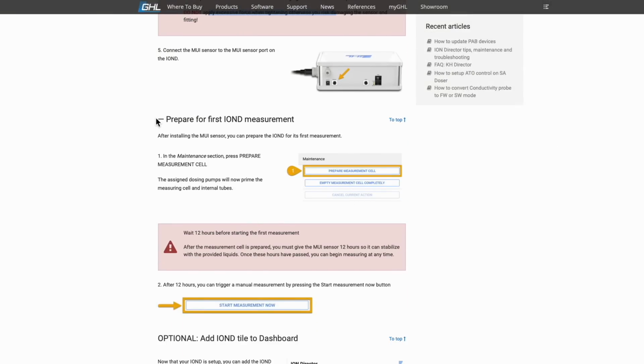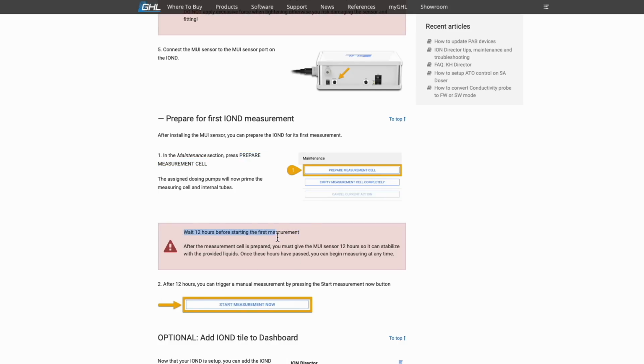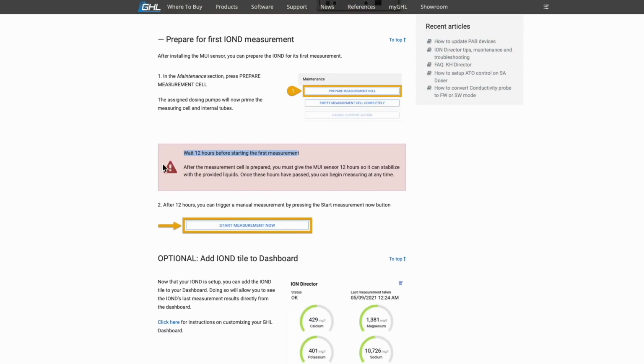Now, after the half-hour wait in the cup of water, I got to this step here, prepare for first Ion Director measurement. So you install the sensor, then you go into the maintenance section and you click Prepare Measurement Cell. It fills up the dosing pumps and primes them and gets fluid in there. Then wait 12 hours before starting the first measurement. Are you kidding me? So I had to wait half an hour with the sensor in a cup. Now I've got to wait 12 hours with this thing sitting there.